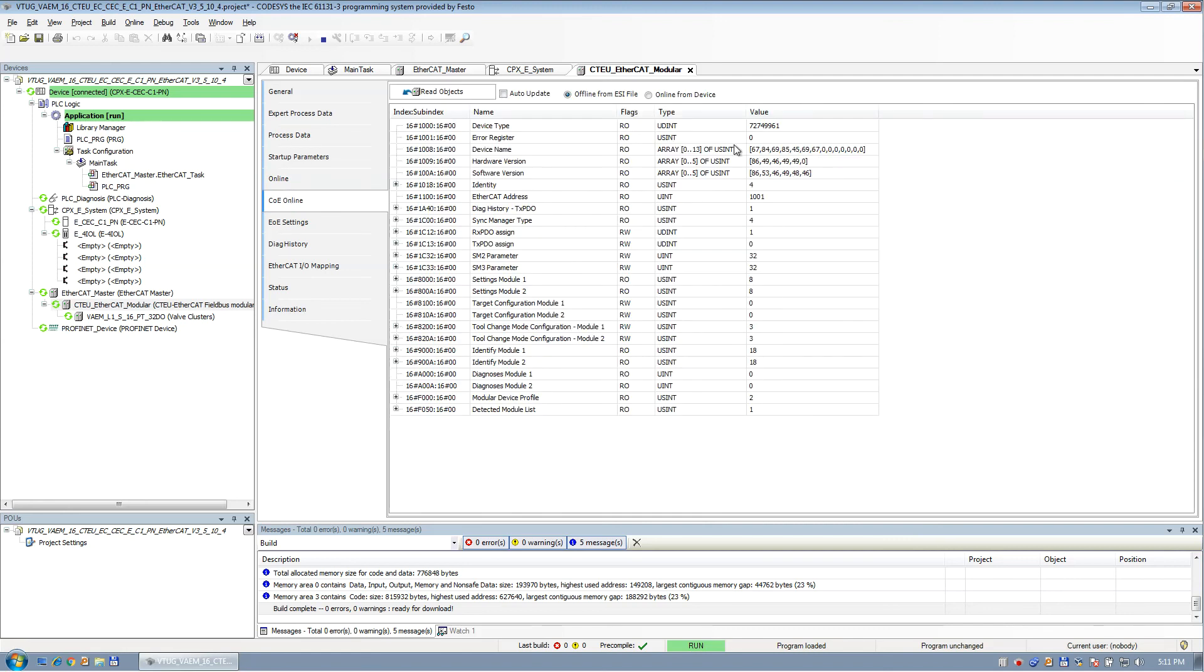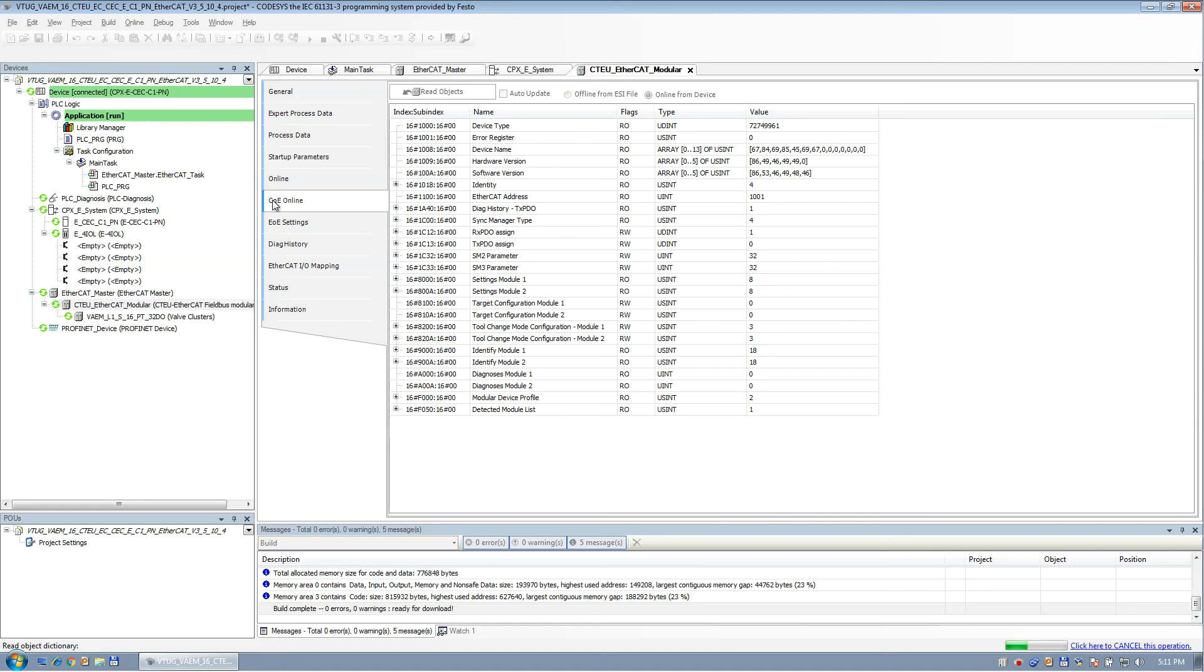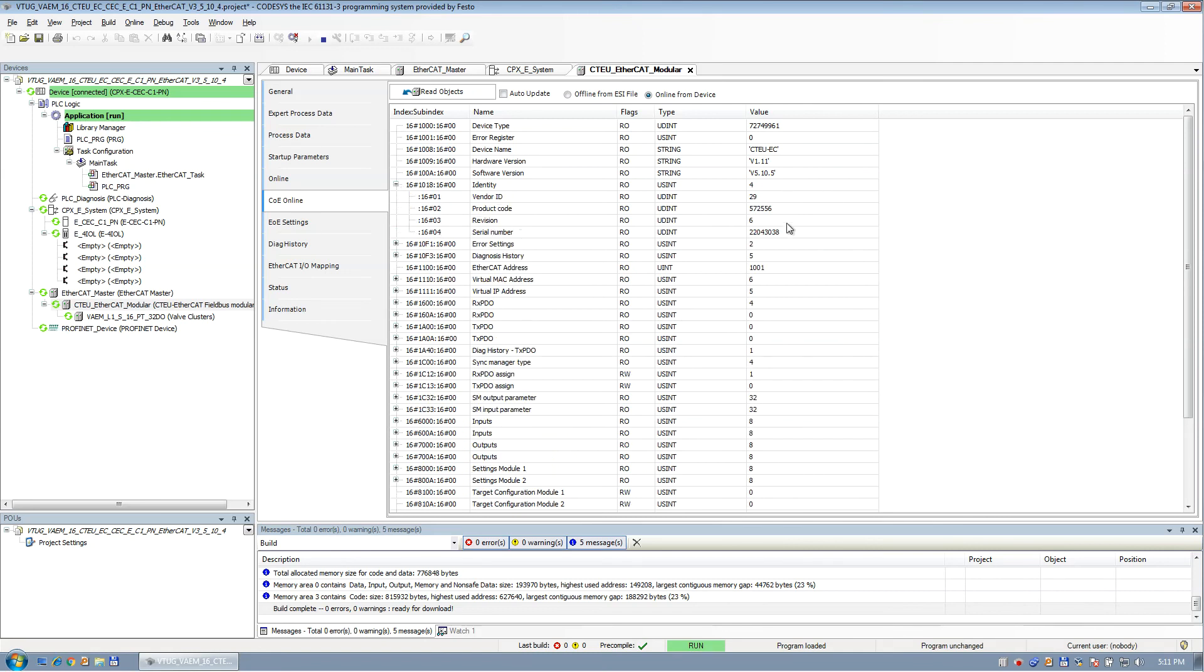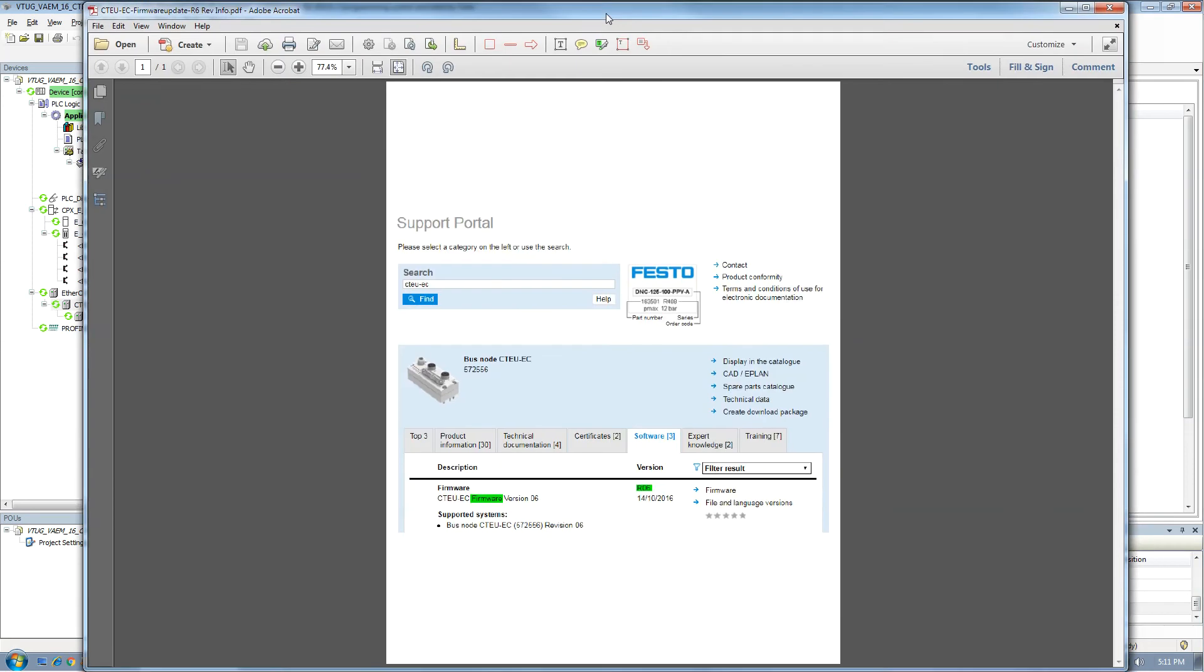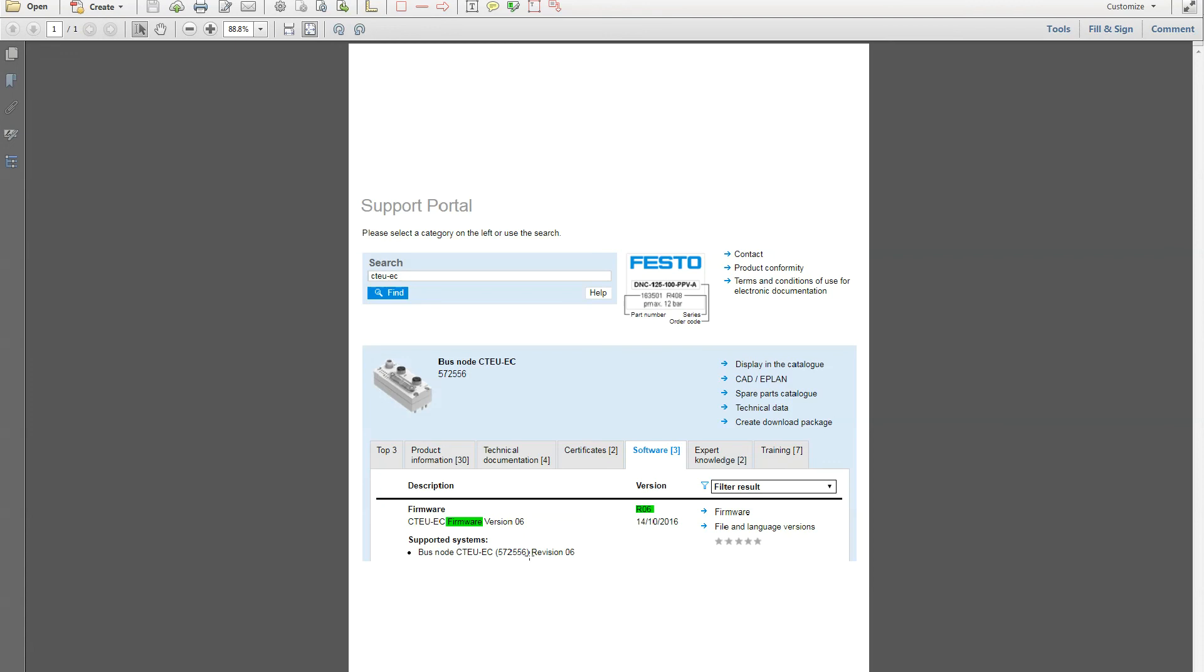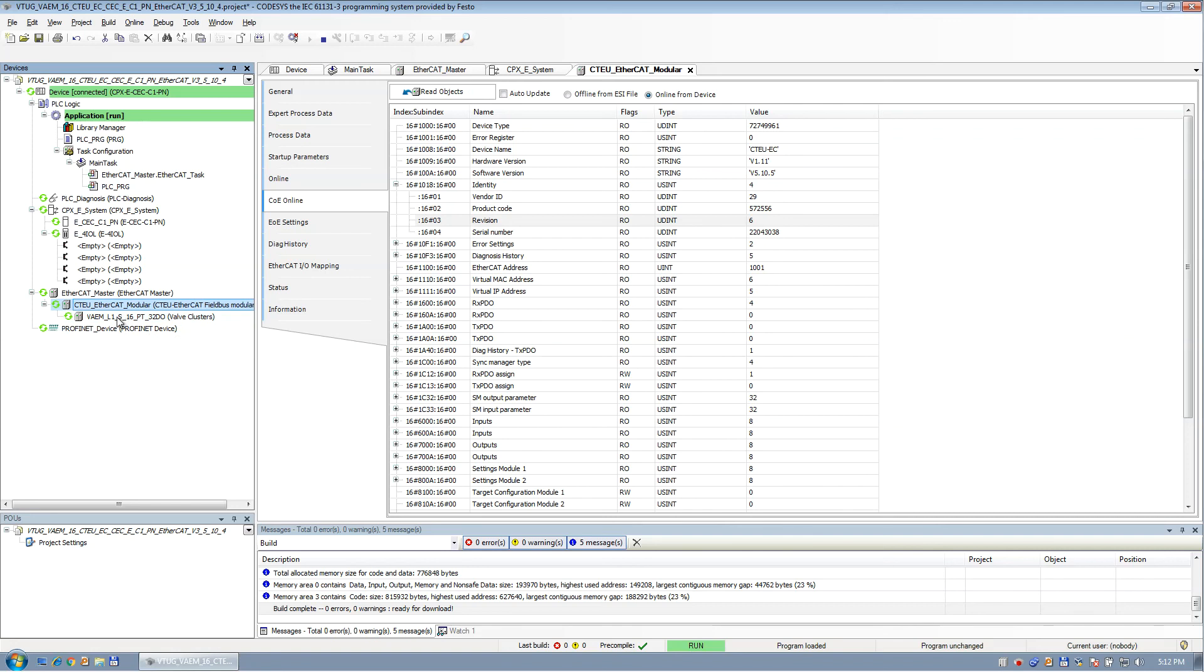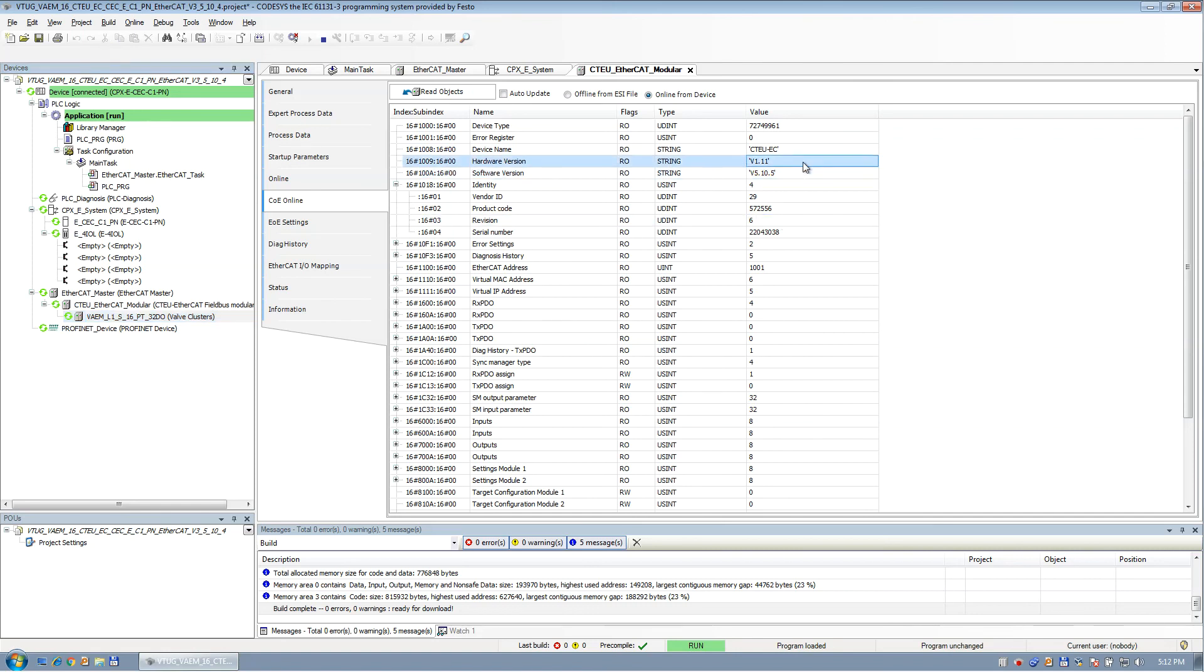The next thing is extremely important. I'm just going to go online from device and look at all the CANopen over EtherCAT values here. I'm going to suck up everything from the device. And we've got an identity. So we're a REV6. And the REV6. If you go to the Festo website here. This is the REV6 firmware. If you don't have a REV6, upgrade it. Find out how to upgrade it. Because I started off a project with REV3, and REV3 does not work with the Service Pack 10 CODESYS. What will happen is every time you cycle power or do anything, it doesn't reset properly. You have so many different little conspicuous problems. So make sure your data revision is at least this number six here. Software version, hardware, and so forth.